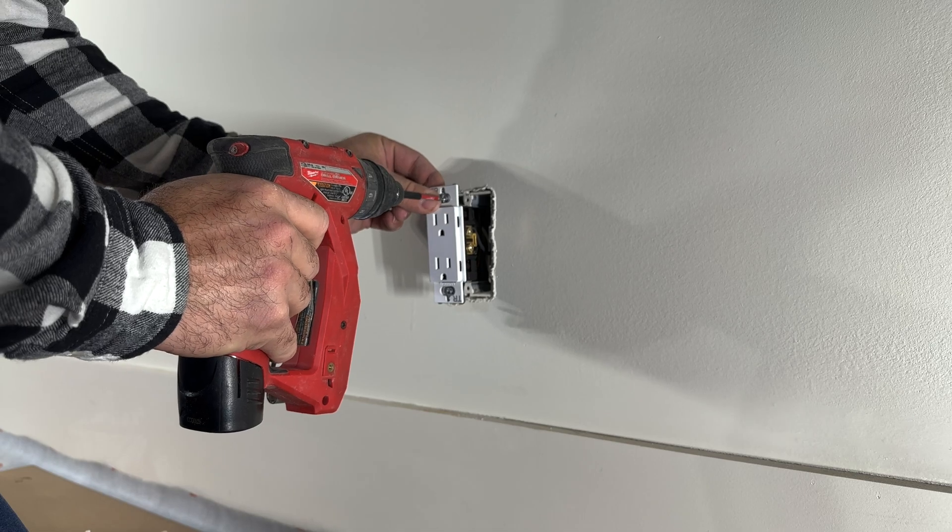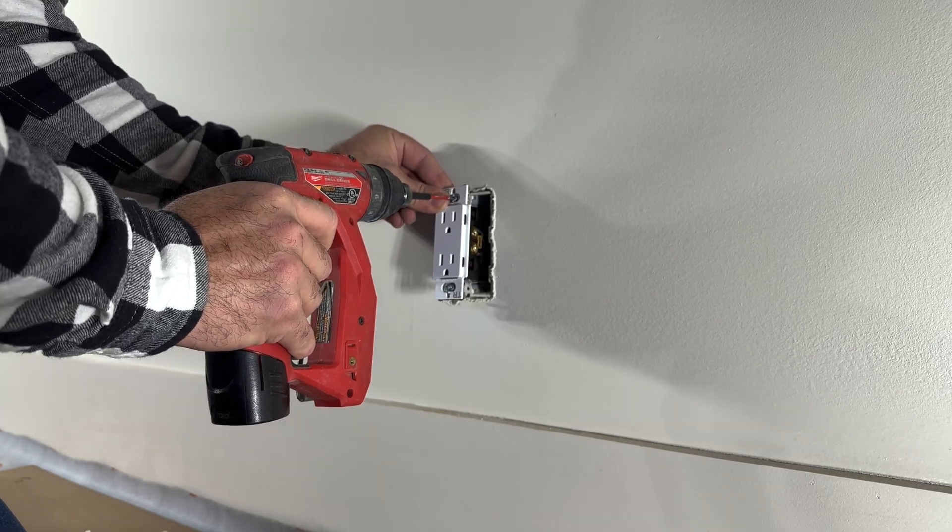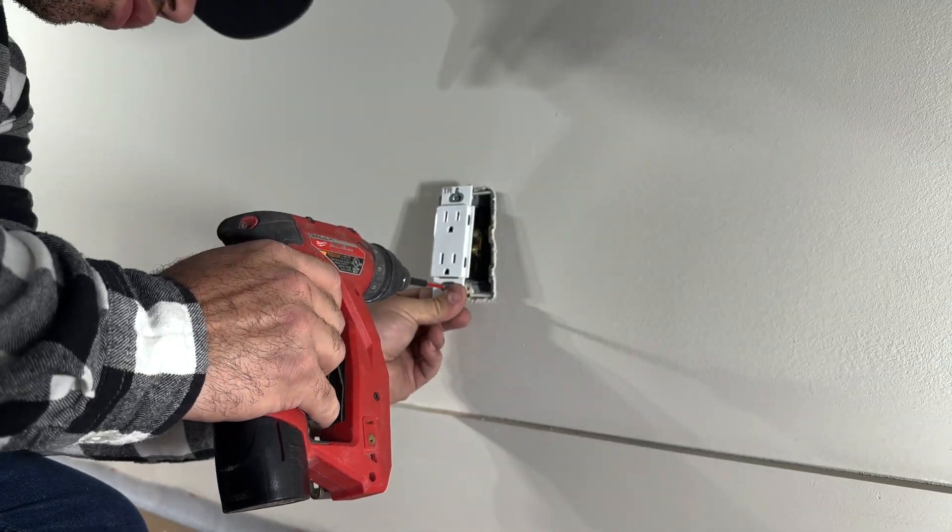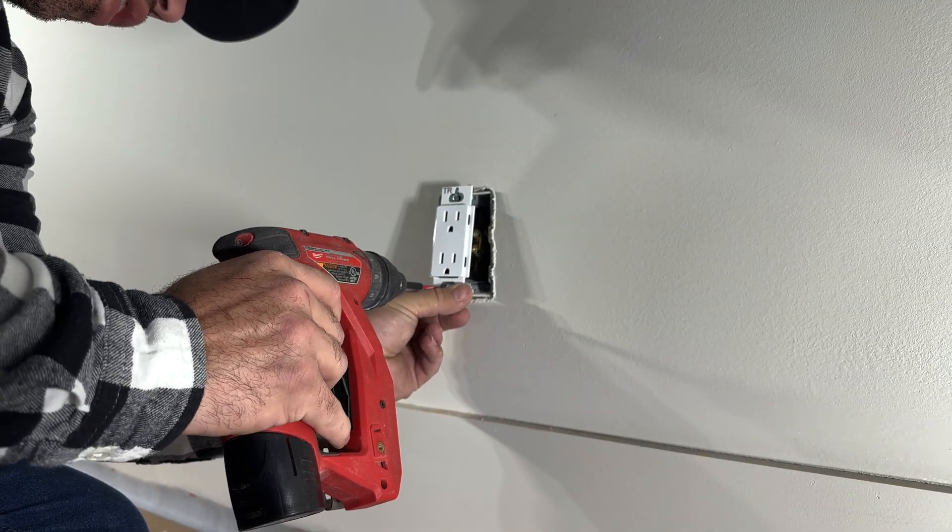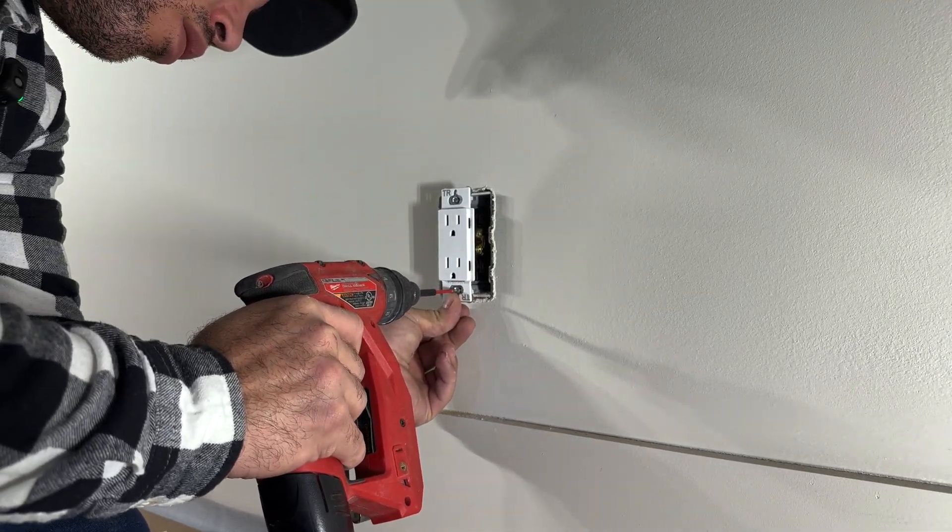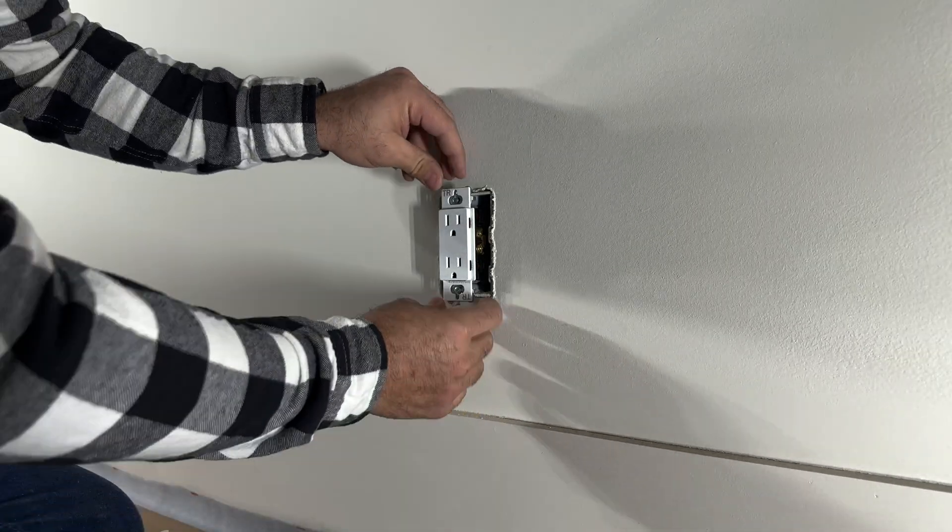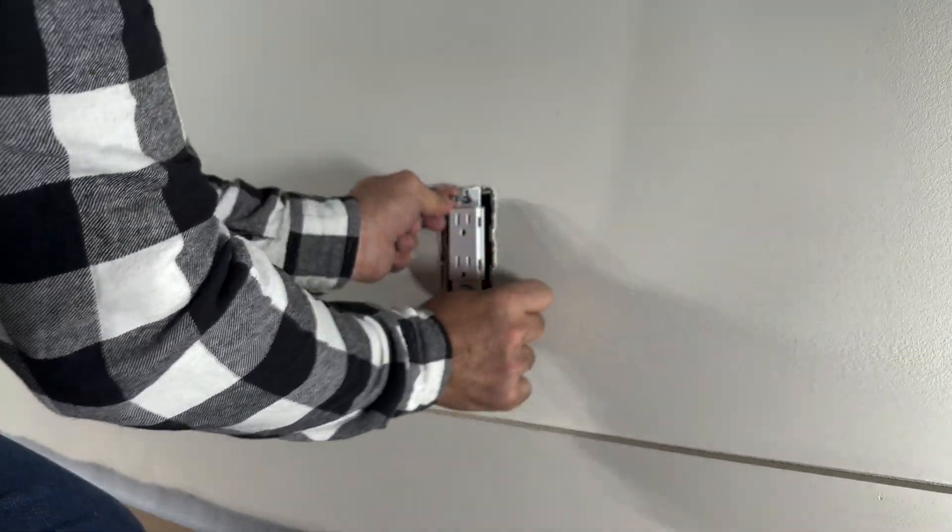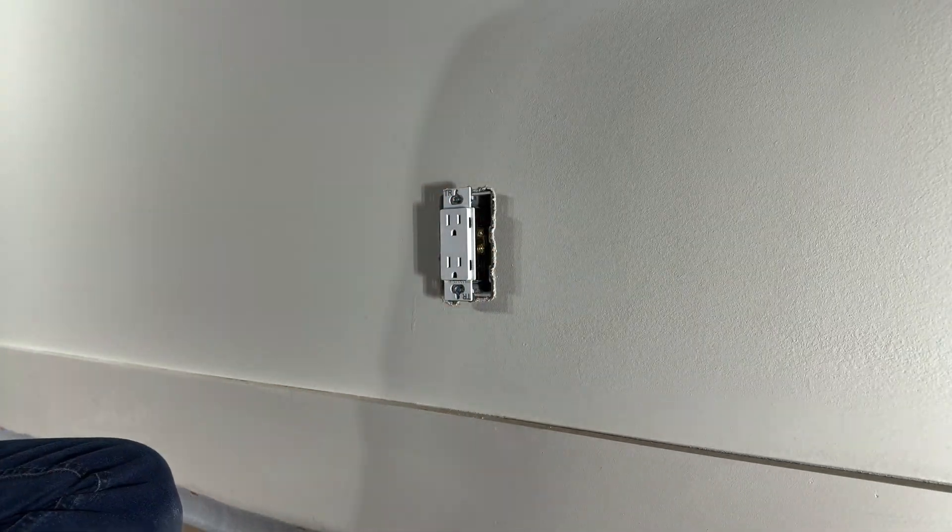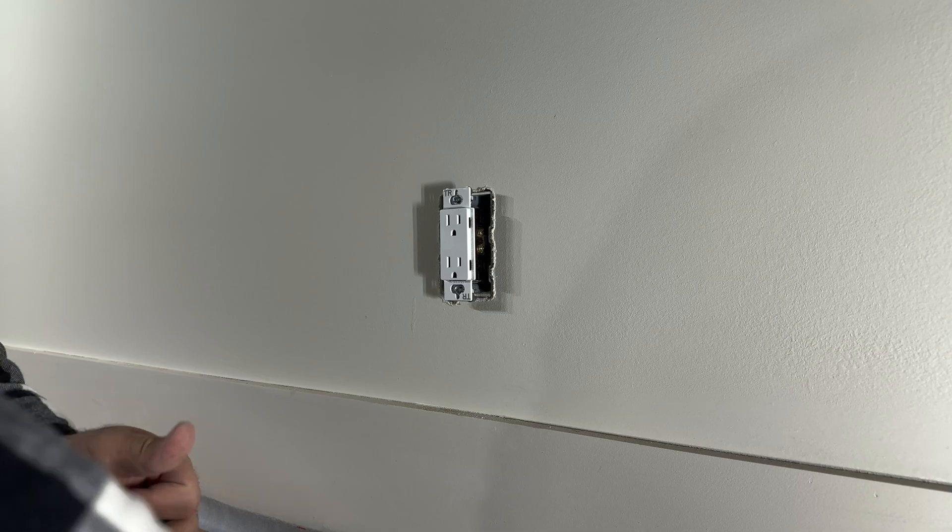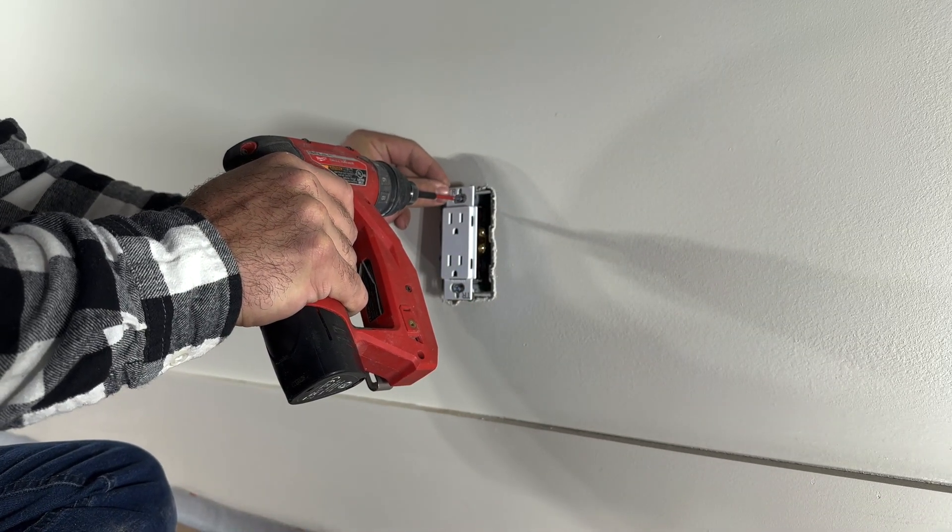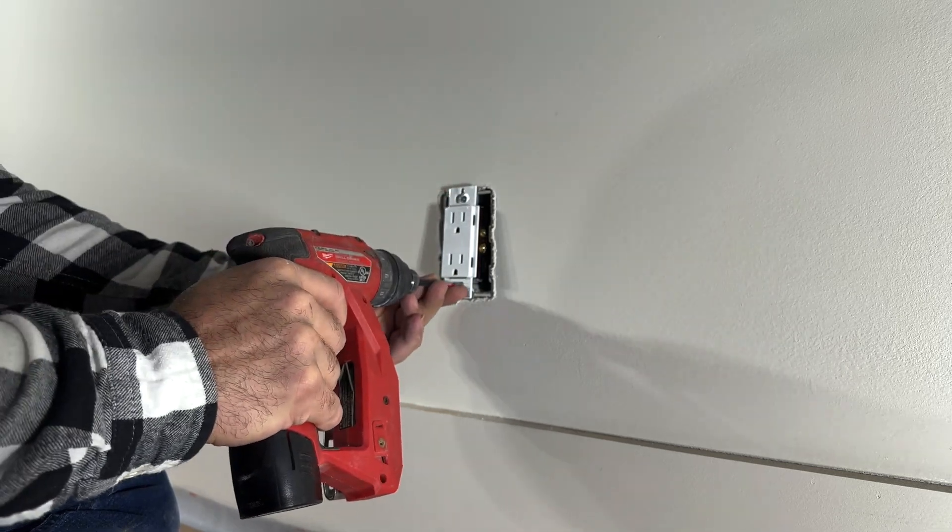Now we will put our receptacle in. What I like to do is just screw a little bit, and then make sure everything is straight. And do this before I tighten it so I don't crush the wires at the back of the box. If it goes smooth, then you know that your wires are not cramped up behind the receptacle.